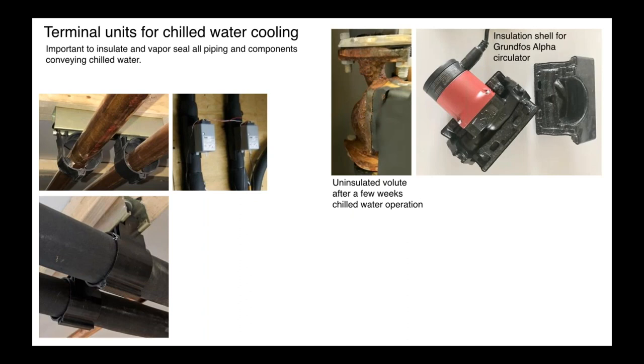Same thing with a circulator volute. Now, just to show you, this is a cast iron circulator, and this would happen with pretty much any brand that I've had any experience with. After a few weeks of chill water operation, you're getting surface oxidation that looks pretty bad. Now, this corrosion isn't eating through the cast iron and eventually causing a failure, but it looks terrible, and it's going to drip on the floor and anything below it. And you can see it extends up onto the flange bolts, even though those are zinc-plated bolts.